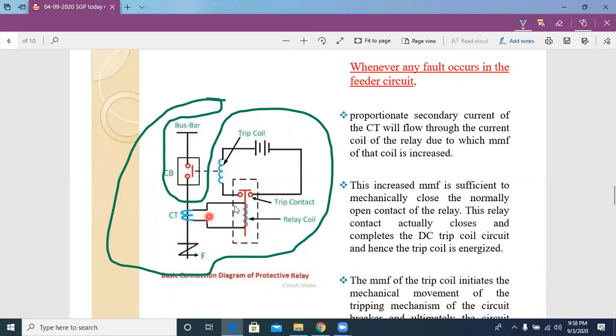Let's assume here we place one relay with circuit breaker. So now let's say, suppose a fault happens in this feeder. When the fault happens, overcurrent flows through the feeder. When the overcurrent flows through the feeder, this particular current transformer sends the current, and according to that, the secondary of this current transformer will give a current to the relay coil. Because of that fault current, the relay coil is excited.